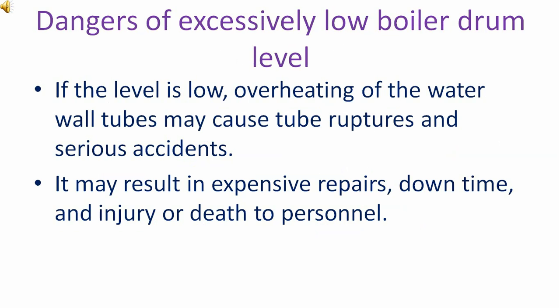Dangers of excessive low boiler drum level. If the level is low, overheating of the water wall tubes may cause tube ruptures and serious accidents. It may result in expensive repairs, downtime, and injury or death to personnel.